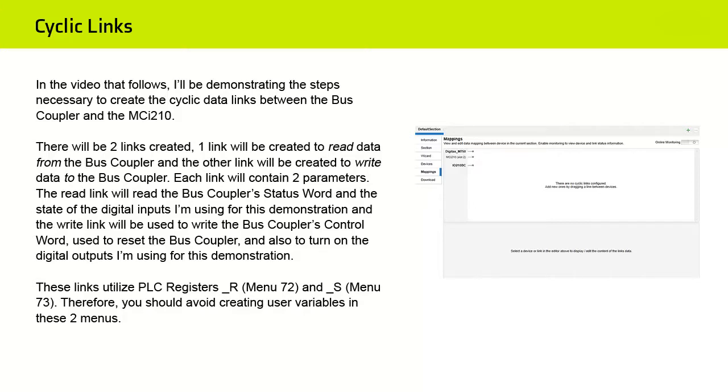These links utilize PLC registers _R, which is menu 72, and _S, which is menu 73. Therefore, you should avoid creating user variables in these 2 menus.